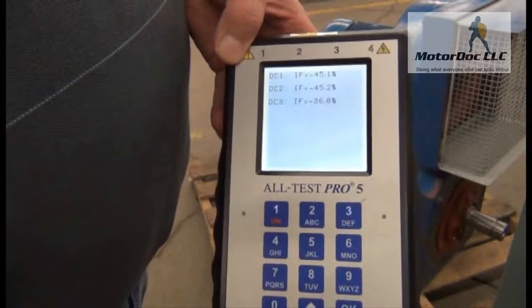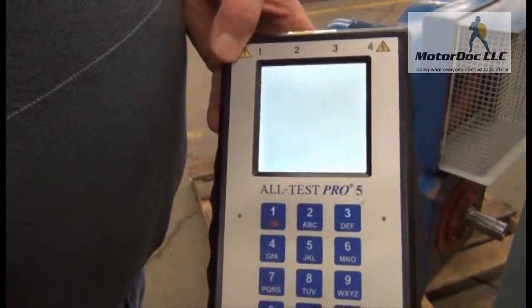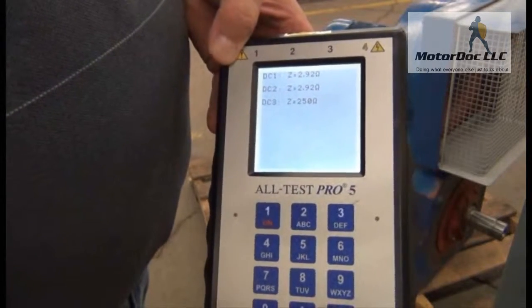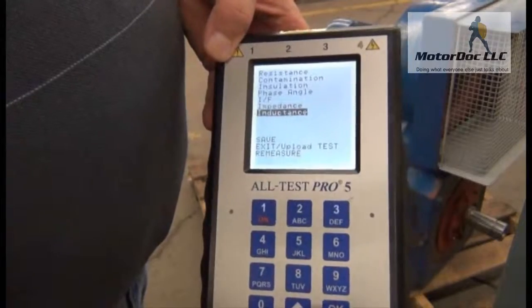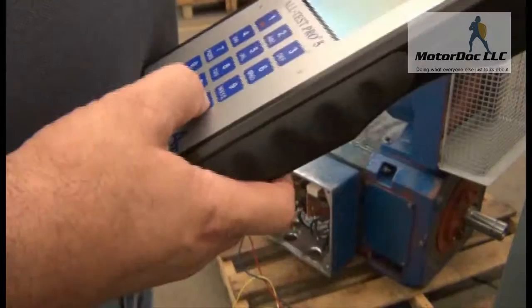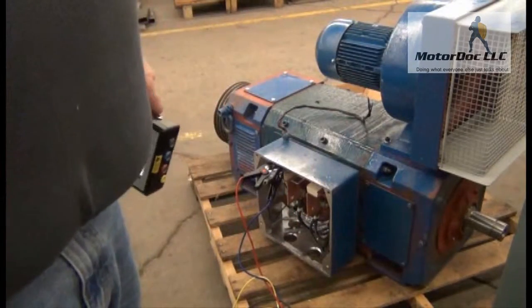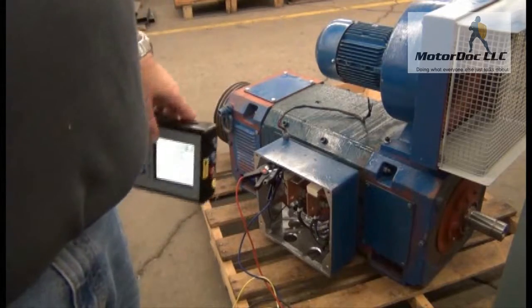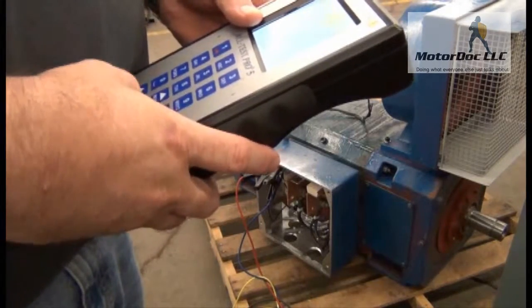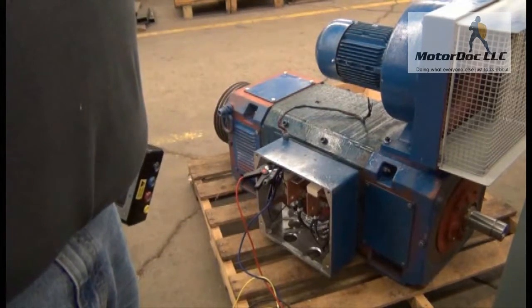Same thing with IF — press OK. Same thing with impedance — press OK. And same thing with inductance. That's the super secret testing you can do with the ALL-TEST PRO 5 to check your armature out without having to disassemble the machine. This works on any size DC machine. Later we'll show you what it looks like when we upload it to the software.